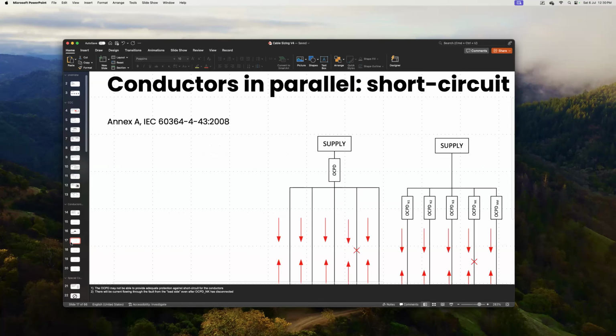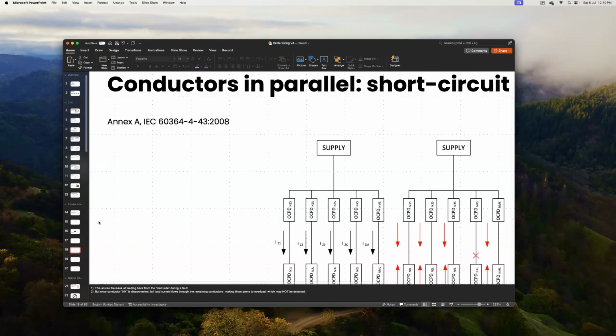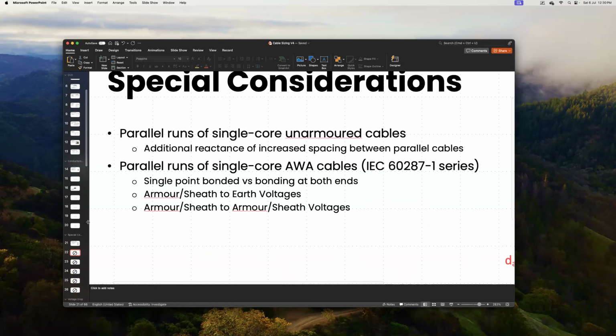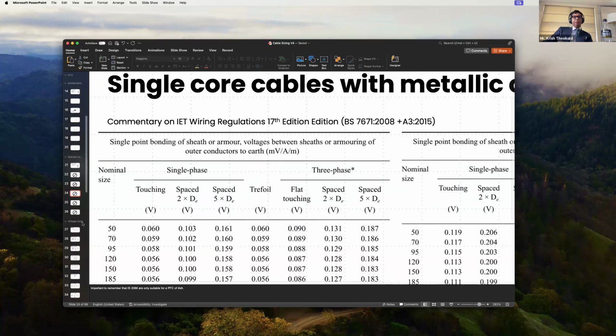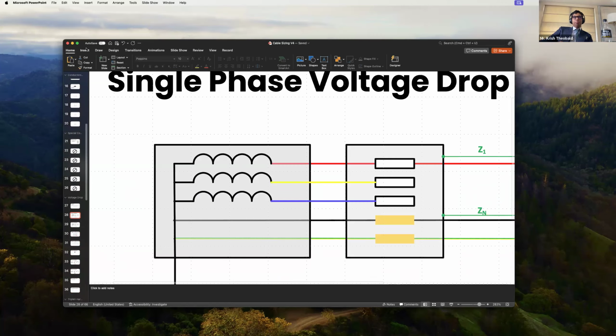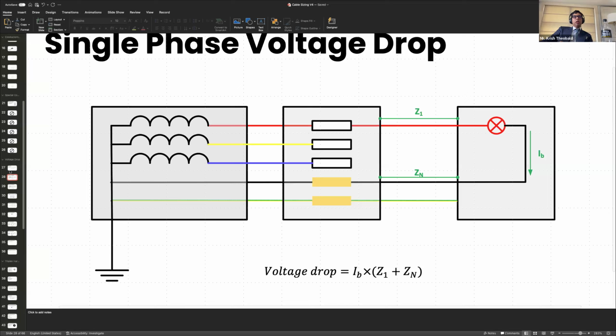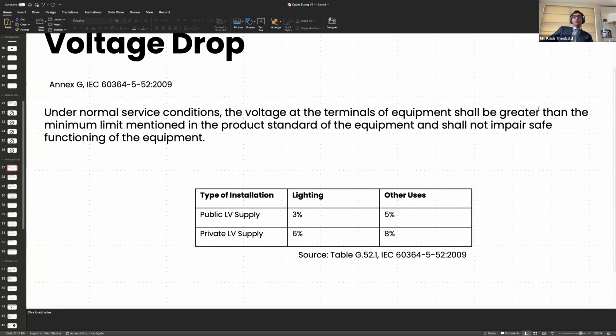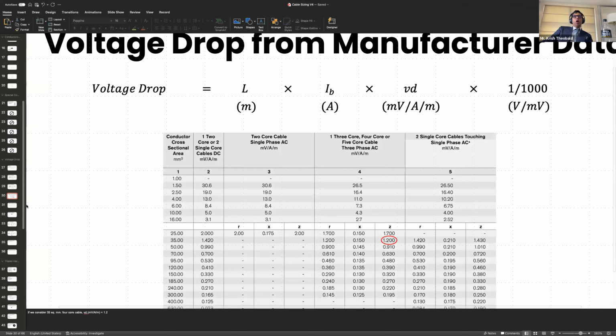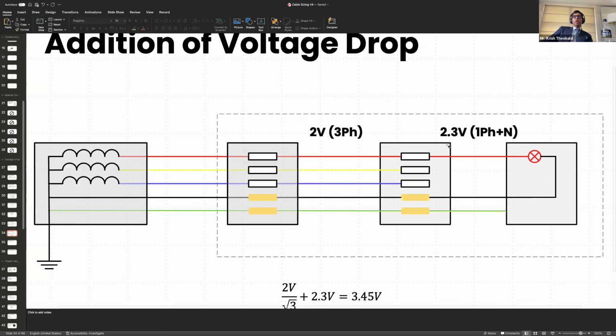Why do we need to restrict the voltage drop to 5% at the end load in industries? Okay, interesting question. You don't. This is guidance, provided where you do not have information from the product standard. In an industry, you will know what the tolerance level is for the equipment. So all you need to ensure is that this voltage drop does not cause a voltage lower than the minimum utilization voltage required for the equipment.